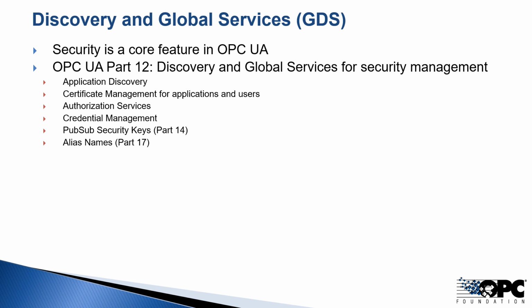Security is a core feature of OPC UA at several levels and will be discussed in different presentations this week. The basic security level is application authentication. Each application, regardless of its role as client, server, publisher, or subscriber, is identified with an X.509 certificate. OPC UA defines user authentication with different types of user tokens and user authorization with role-based security, and the ability to set permissions down to node attributes such as read or write access to a variable value.